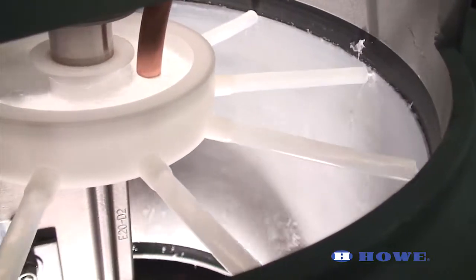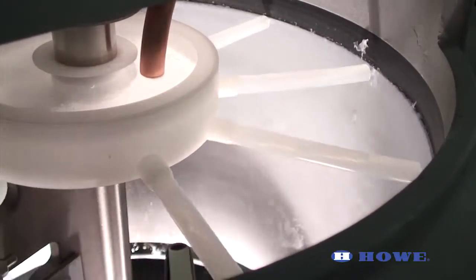After adjustment, do a final visual check to ensure proper ice freezing and harvesting over the entire evaporator.